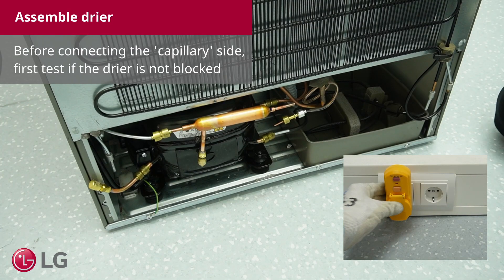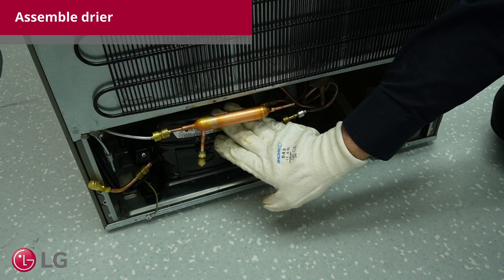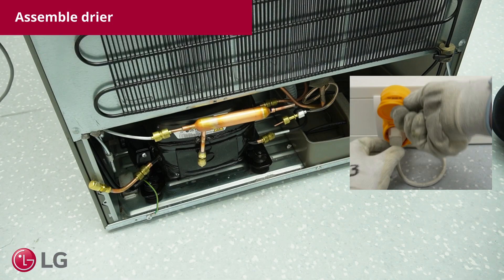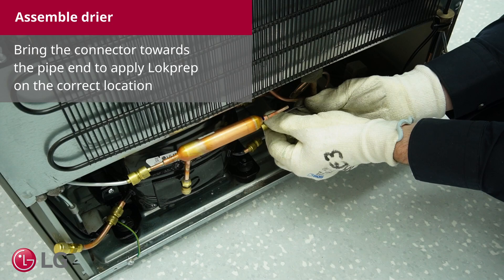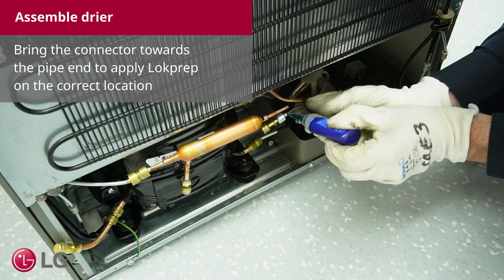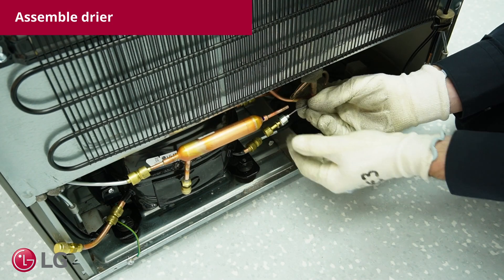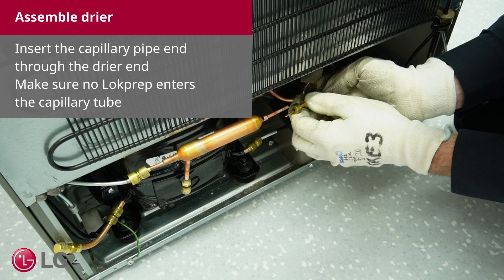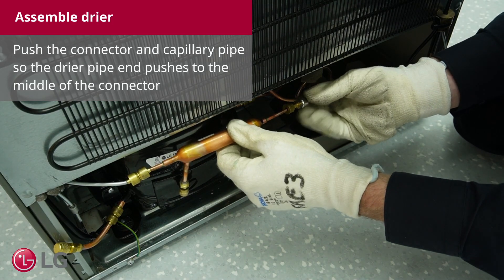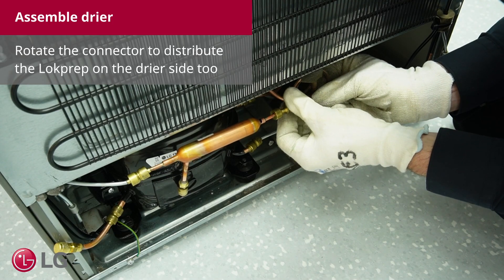Before connecting the capillary side, first test if the drier is not blocked. After plugging in the power, wait until the compressor starts. Unplug the power. Bring the connector towards the pipe end to apply Lokprep on the correct location. Push the connector towards the bent side and rotate to distribute the Lokprep. Insert the capillary pipe end through the drier and make sure no Lokprep enters the capillary tube. Push the connector and capillary pipe so the drier pipe end pushes to the middle of the connector. Rotate the connector to distribute the Lokprep on the drier side too.